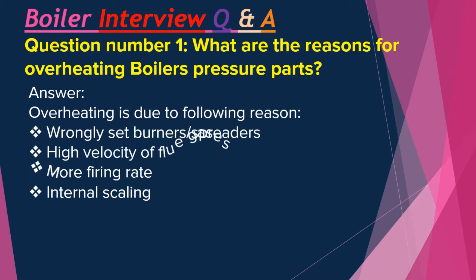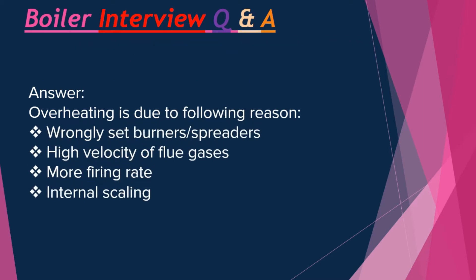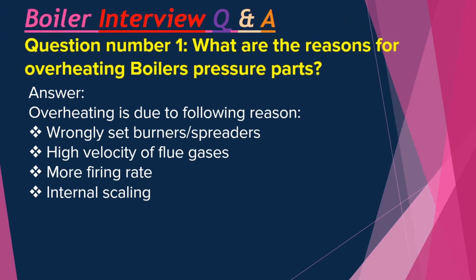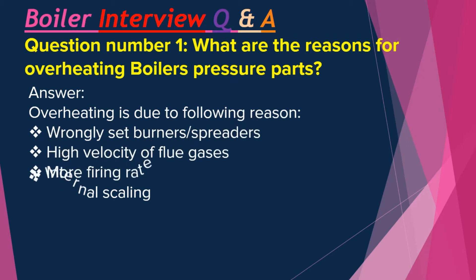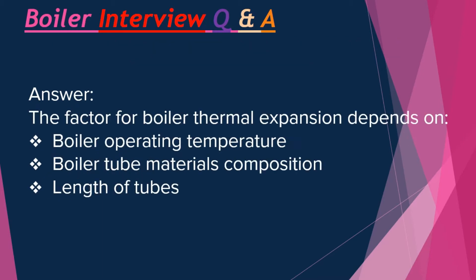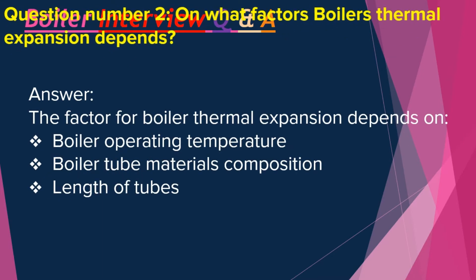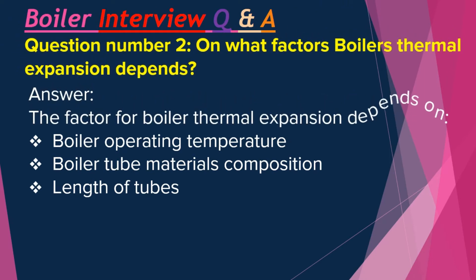Question number one: What are the reasons for overheating boiler pressure parts? Answer: Overheating is due to the following reasons — wrongly set burners or spreaders, high velocity of flue gases, more firing rate, and internal scaling.